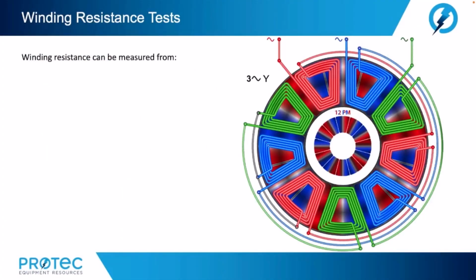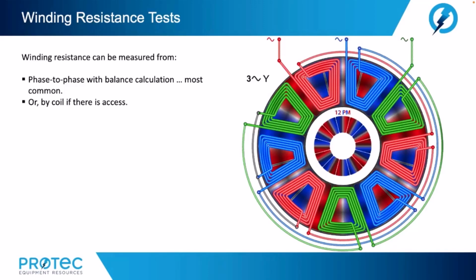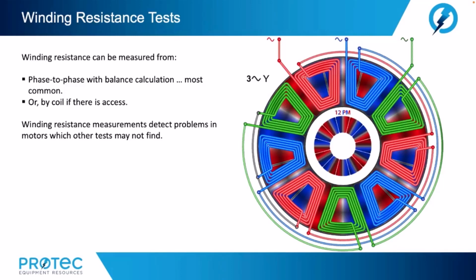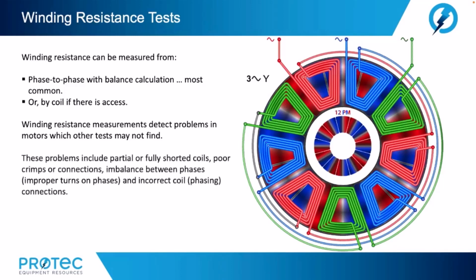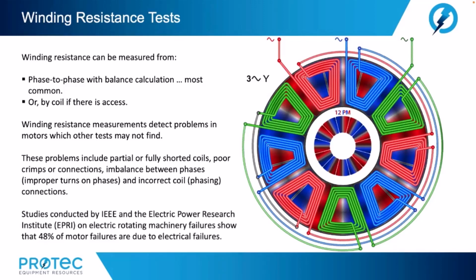Let's start with that winding resistance test. Winding resistance can be measured from phase to phase with balance calculation, which is most common, or by coil if there is access. Winding resistance measurements detect problems in motors which other tests may not find. These problems include partially or fully shorted coils, poor crimps or connections, imbalance between phases, improper turns on phases, and incorrect coil phasing connections.